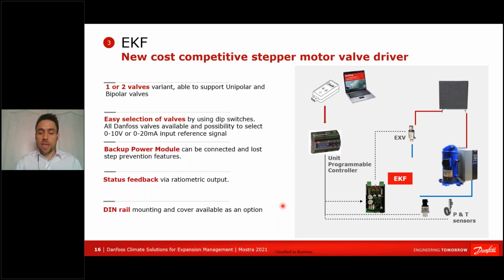Basically, you can set the EKF quite easily with dip switches. It's pre-configured for all the Danfoss valves, but you can also configure any kind of valve. For that, you just need a USB stick, and then you can upload the custom settings on the EKF. So the EKF board is just a translator of electrical signals, which makes it very versatile and very cost competitive. It can also be plugged with a power backup module, which makes it quite nice in case of emergency failure, as I was discussing before. And last but not least, it has a status feedback. The main controller often wants to know the status of the valve, and the EKF is able to get the status and feed it back to the main controller.